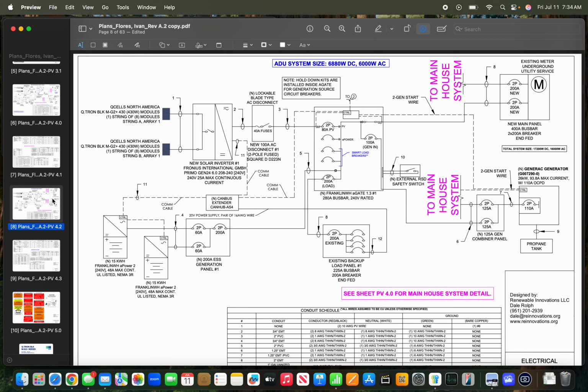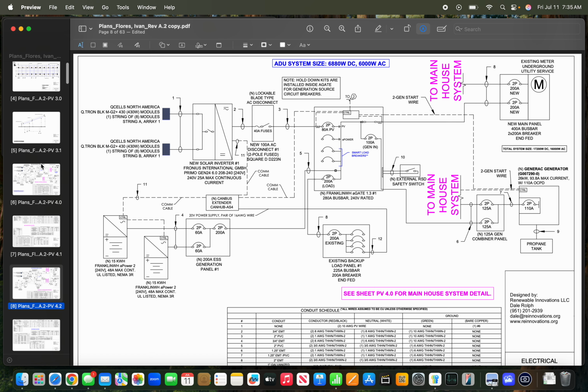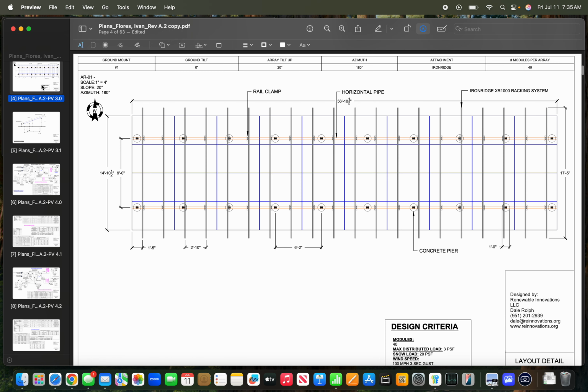What's nice about the Franklin equipment is it supports rapid shutdown. There will just be 2 safety switches near the main electrical panel, and a first responder can turn that knob, and the batteries and solar equipment shut off completely safe and self-contained. The DC energy is contained at the array, so they don't have to worry about any DC energy coming from the array up to the house.